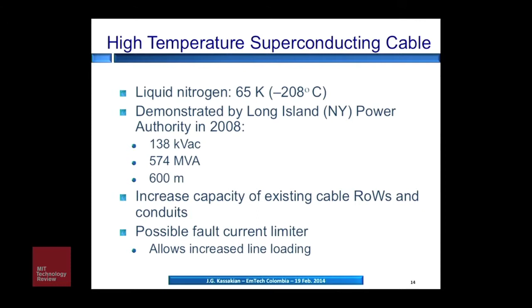Another technology that is very new, the technology itself isn't new, but its application to power systems is the high-temperature superconducting cable. And the interesting thing about the high-temperature superconducting cable is that in the same size as a conventional cable, in the same ducts, in the same space, you can put a superconducting cable that will increase the capacity of that right-of-way, the capacity of that line, by a very substantial amount. What this means is that you don't have to get new right-of-ways, you don't have to dig new trenches, you don't have to put in new conduits.